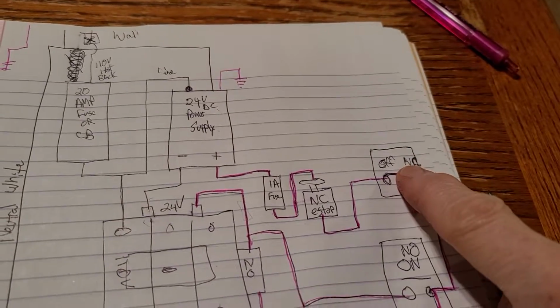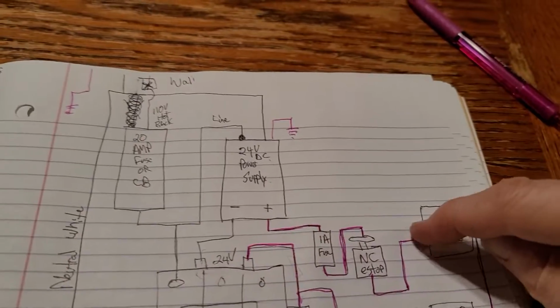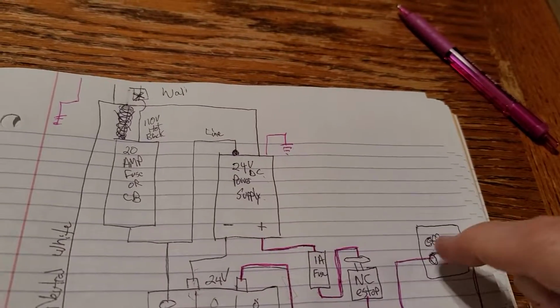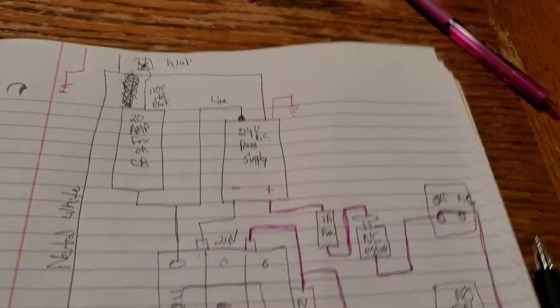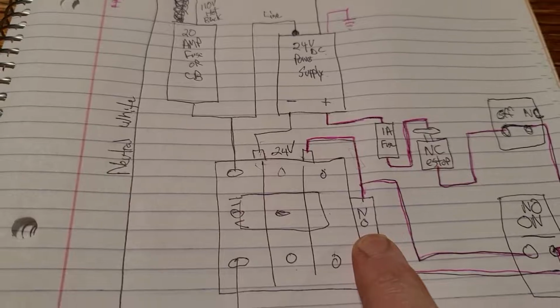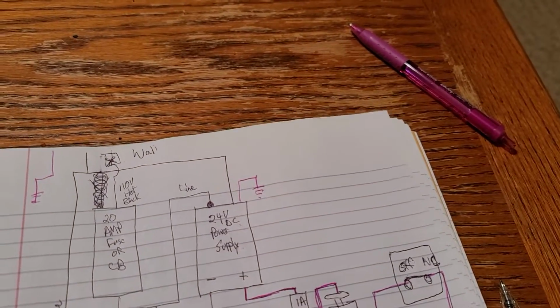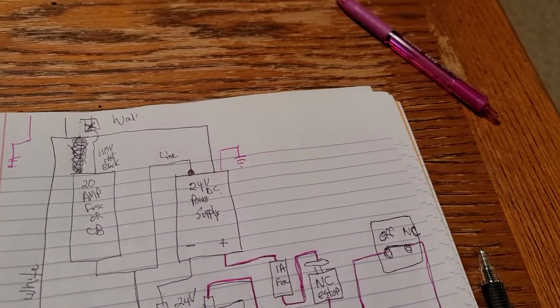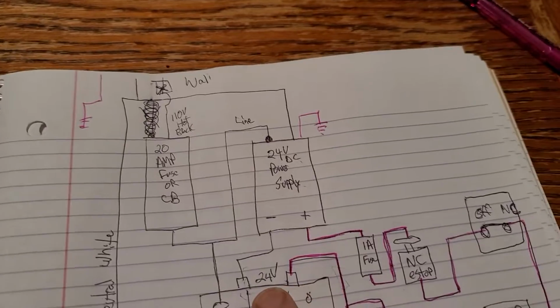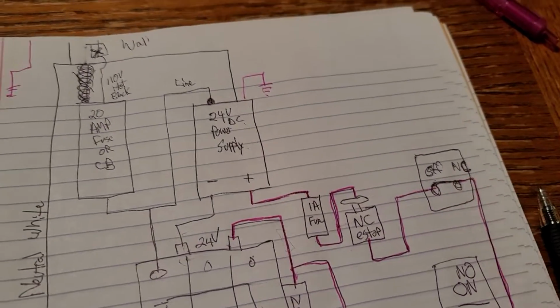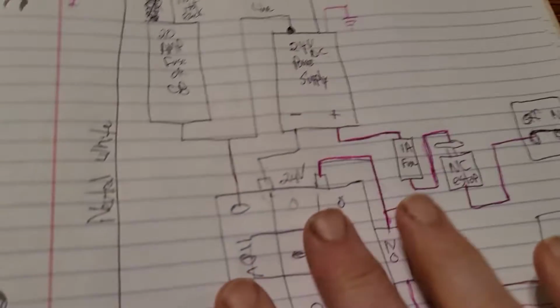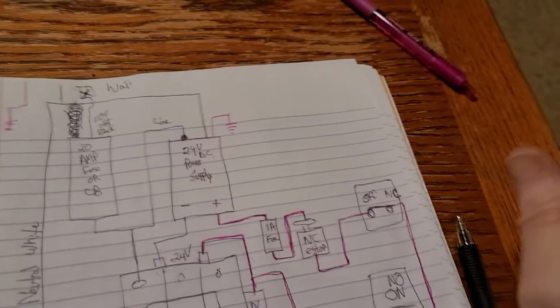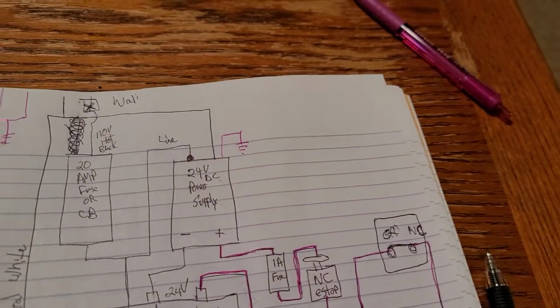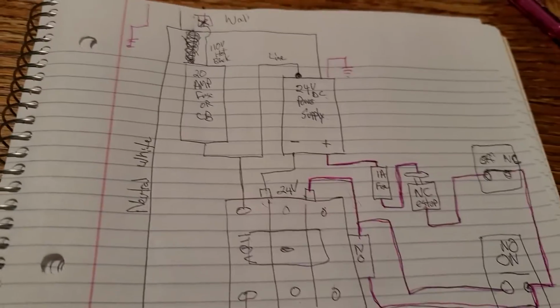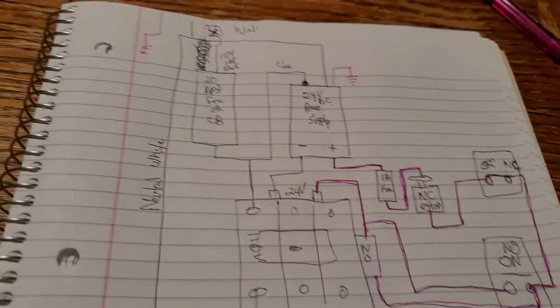Well, when we hit this button here, the off button, now it opens. Okay? Now there's no longer power applied here, right? If there's no power here, that means there's no power going over to this normally open section. Okay? It's not going through, or actually it is going through, but when there's no power going through, this is closed because it's on, it's no longer going to the coil because we broke it there. We broke it over here. So now this power goes away. There's nothing latching that coil. This then opens. It goes back to its normally open state. So then, even though we let off the off button and power comes back through there, this is no longer closed. And that's why the power doesn't suck it back in here. That's how a contactor works.